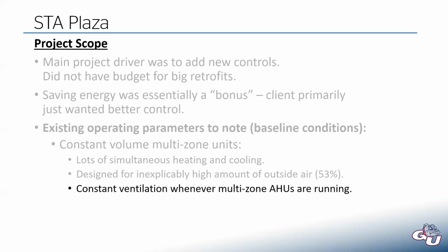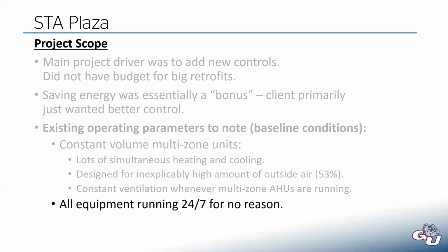And these were designed to provide constant ventilation air, so a constant amount of CFM whenever those multi-zone units are on. So all the time they're providing 53% outside air, which is a lot. And all of their equipment was running 24/7. And I mentioned, if I hear that they're running their equipment 24/7, that's when I really perk up and start thinking, oh man, there could be some really good opportunity here to save some energy.